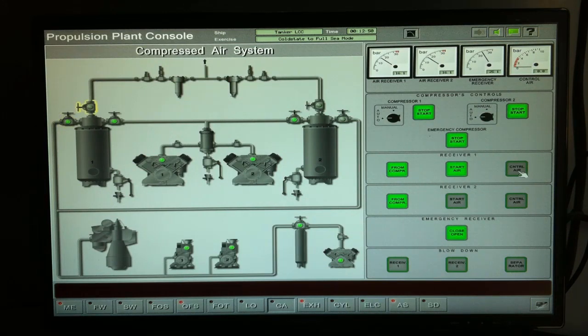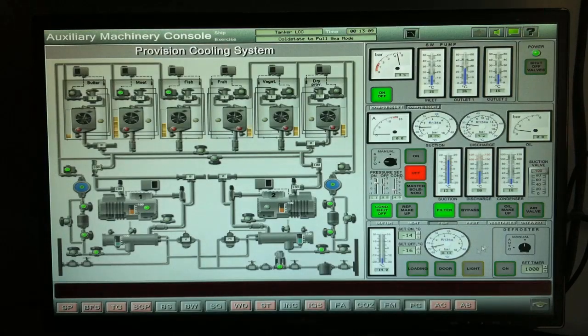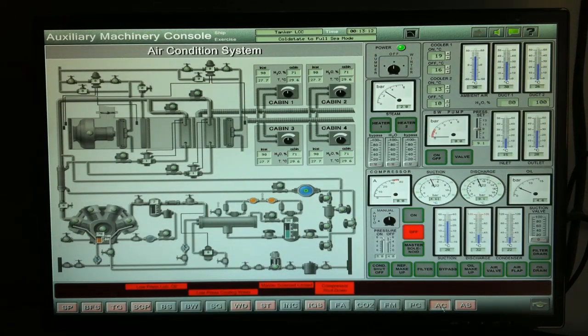We can open now starting air, control air valves, and could already now stop your emergency compressor, close your emergency receiver. Okay, so for the meantime, while waiting for the steam pressure to rise to around 20 bars, we proceed back to the auxiliary machinery. We check on the air conditioning plant. We need to start the aircon. So set your aircon to summer mode. Adjust pressure setting of the seawater pump to the condenser.